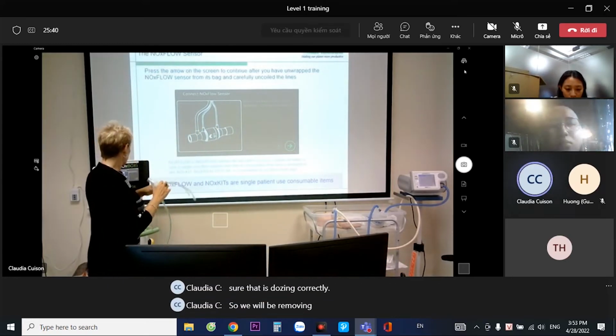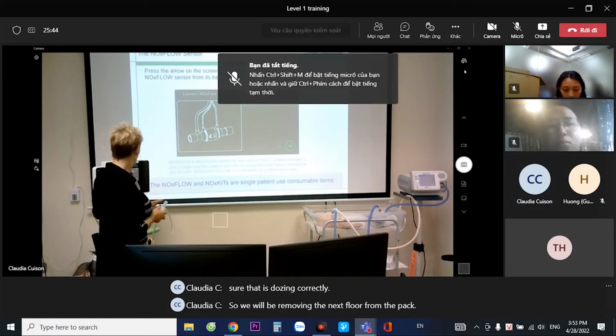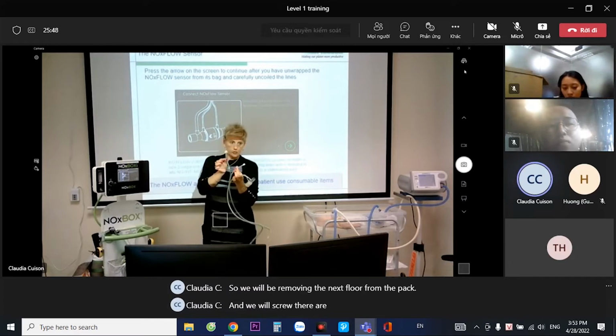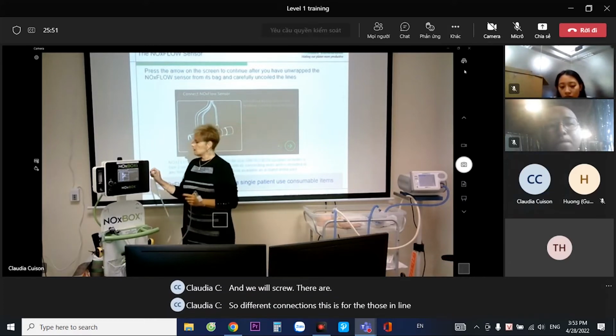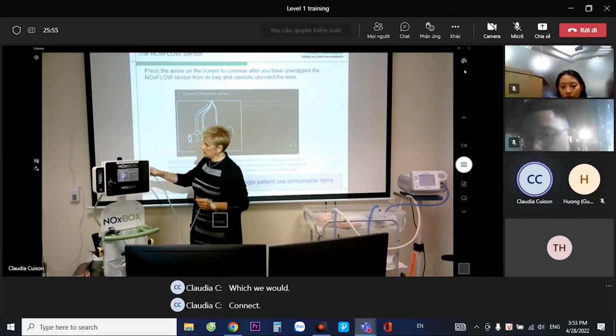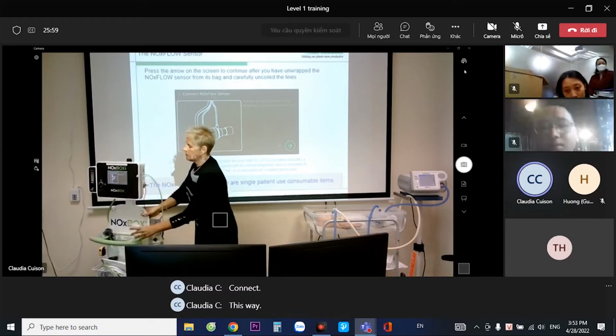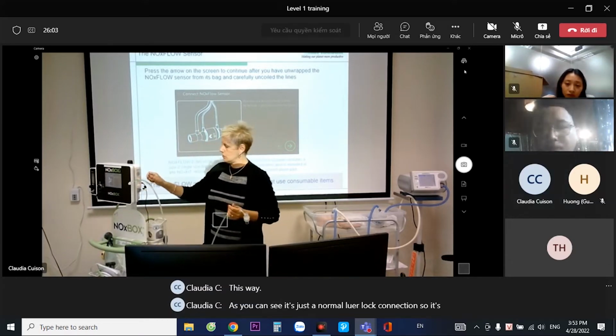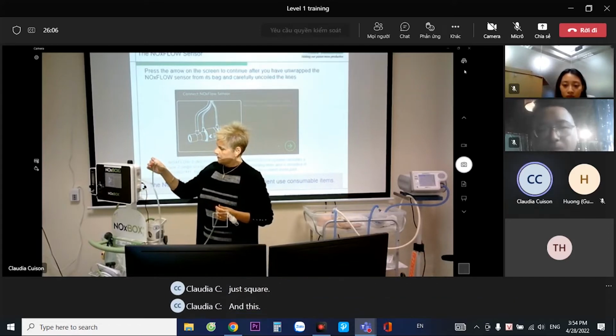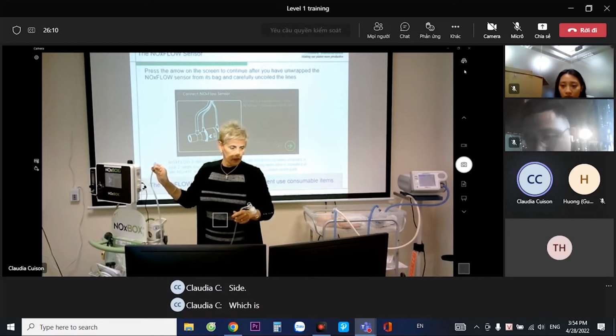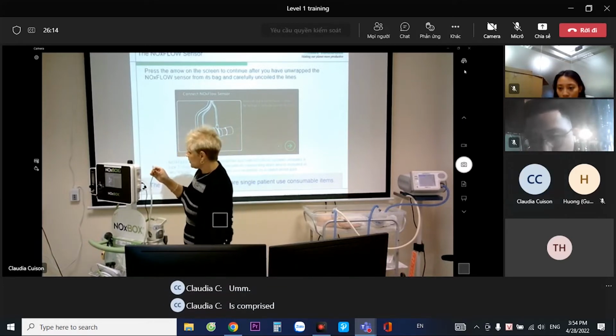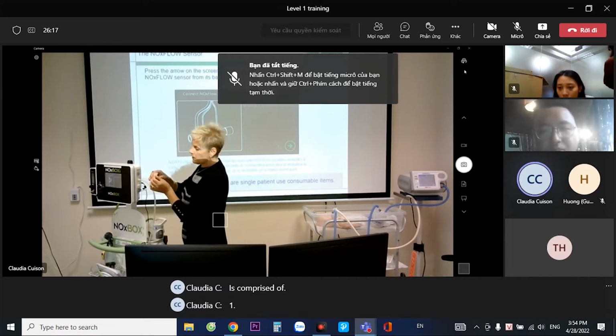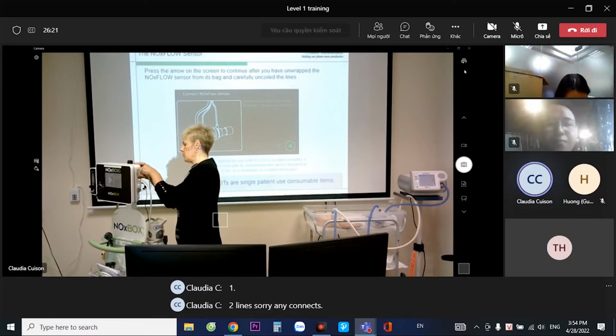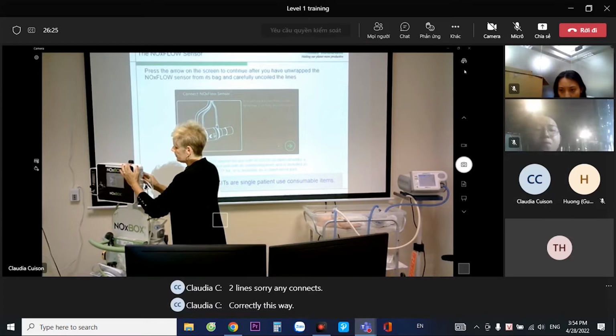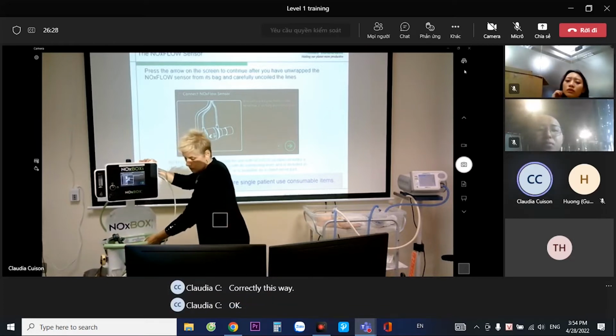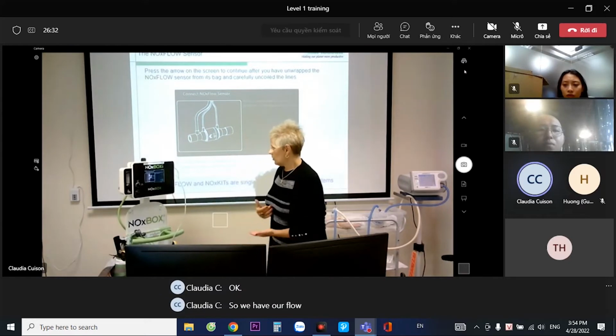So we will be removing the NOx flow from the pack. And we will screw. There are two different connections. This is for the dosing line, which we would connect this way. As you can see, it's just a normal luer lock connection, so it's just screwing. And this side, which is comprised of two lines, sorry, connects correctly this way. Okay. So we have our flow detection connected, or NOx flow.